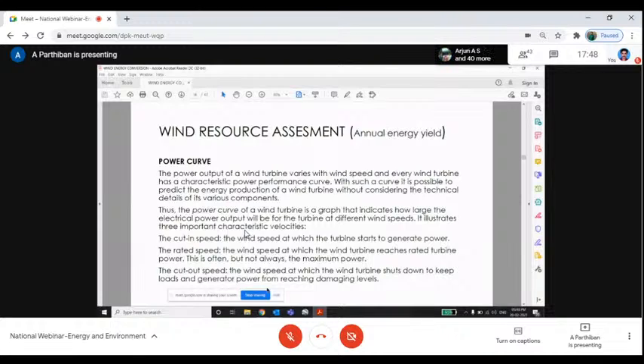In the power curve, there are three major portions: the cut-in speed, the rated speed, and the cut-out speed. What is cut-in speed? At 1 meter per second and so on, the wind turbine will not work. We need a particular cut-in speed, 3 meter, 4 meter like that. Cut-in speed is where the turbine will start generation of power. The second one is the rated speed, the particular wind speed at which it has full capacity. For example, if a 2 megawatt turbine generates 2 megawatt at a particular wind speed, 12 meter or 13 meter, that is the rated speed.